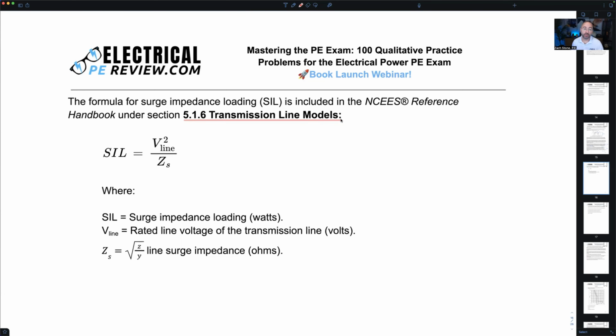It's really interesting to point out, what are my units for surge impedance loading? This is in units of watts. So we can calculate the surge impedance loading all day. If I come across a quantitative question, if it says calculate the surge impedance loading, I go in the reference handbook, I see my formula, I punch in the numbers, and I select the answer. But the formula by itself is not enough to answer that qualitative question.